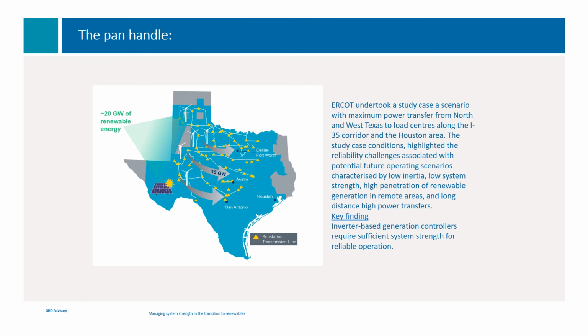This is what the Texans use to call the Panhandle. It's a map of Texas. And as you can see, there's a significant amount of renewable generation in the west, whereas the load centres tend to be in the east and south. ERCOT undertook a study of a scenario with maximum power transfer from north and west Texas to load centres around the I-35 corridor. The study case conditions highlighted the reliability challenges associated with the potential future operation scenarios characterised by low inertia, low system strength and high penetration renewable generation.